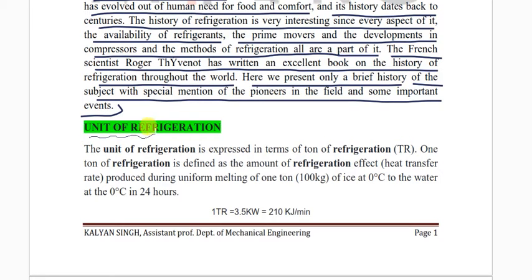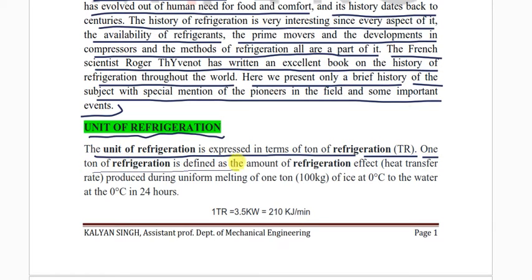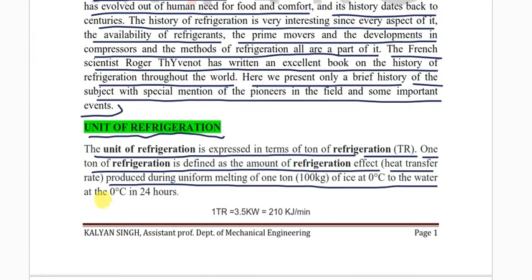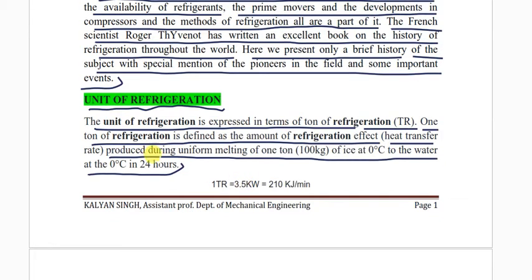The unit of refrigeration is expressed in terms of tonne of refrigeration, TR. One tonne of refrigeration is defined as the amount of refrigeration effect — the heat transfer produced during uniform melting of one tonne (1000 kg) of ice at 0°C to water at 0°C in 24 hours.